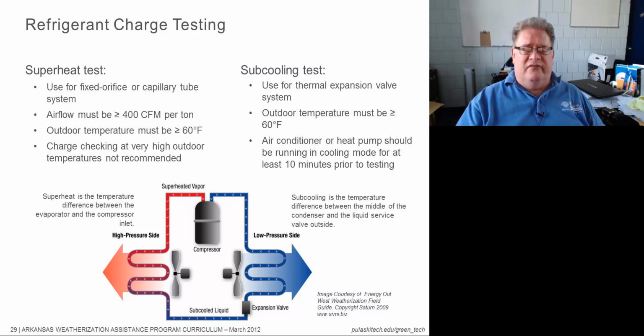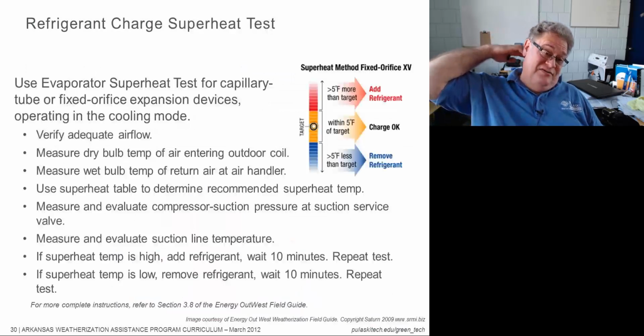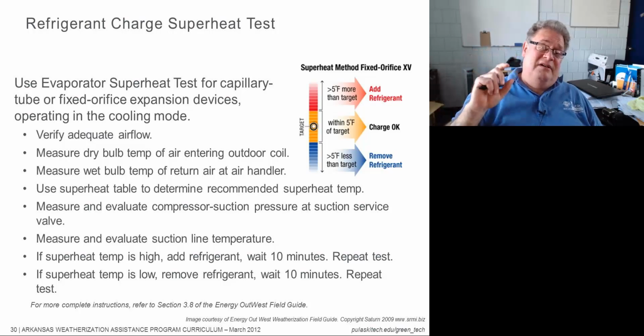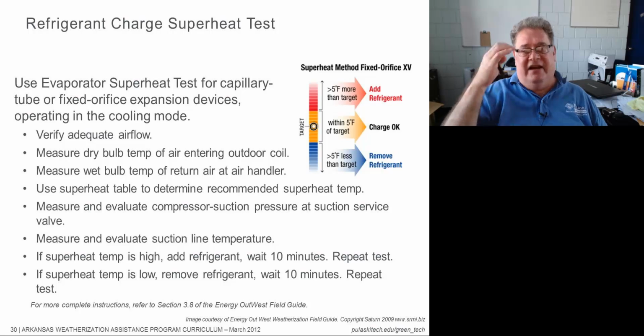This is why it's good for a quality control inspector to understand what the test is and how it should be run, so that they're not seeing something that is not true when they have an unqualified HVAC person out there messing with the refrigerant. So for the refrigerant charge superheat test, we want to use the evaporator superheat test, again, for capillary tube or fixed orifice expansion valve devices.